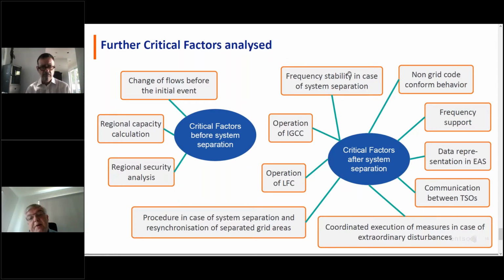After system separation, there are several things we have to take a look at. If we have a European-wide system of netting of imbalances, which is IGCC, which allows one country to net its imbalance with another. For instance, if France is 100 megawatts too much and Germany is 100 megawatts too little, this can be netted, and both countries are then immediately stable thanks to IGCC. Of course, netting should not happen when the system is split, because then you'd have the adverse effect, netting imbalances over a split system, which could make the situation even worse.